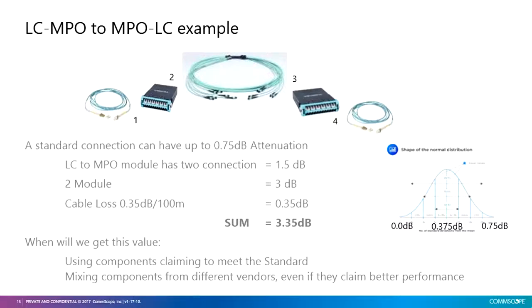When will we get this value? Using components claiming to meet the standard. And I want to insist here, when mixing components from different vendors, even if they claim better performance, we have to follow the standard values, which will be 3.35 dB.